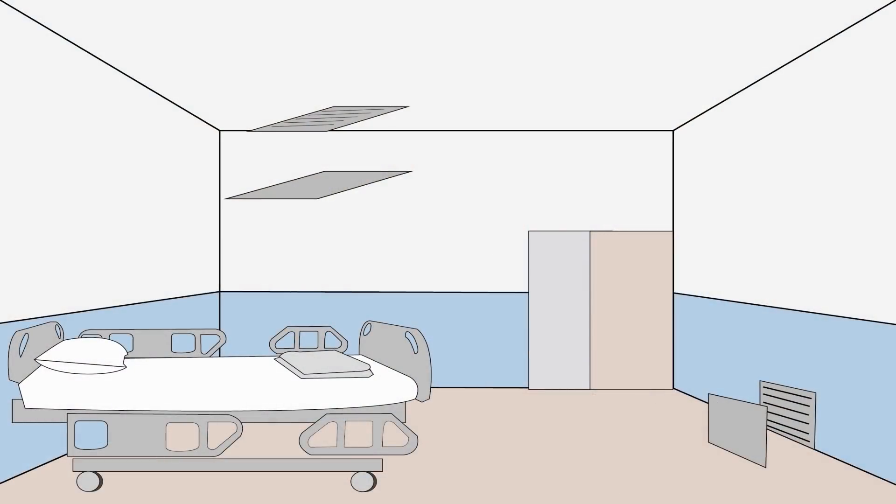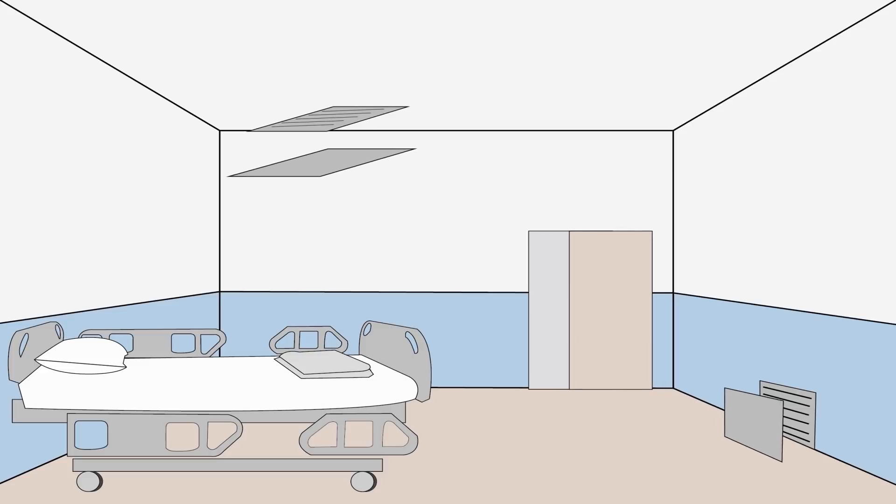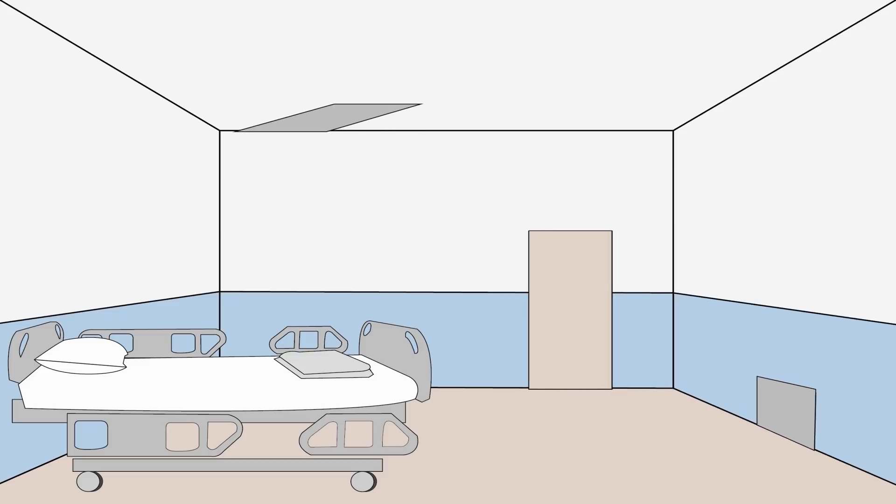To create an isolation space, you have to cut the room off from the rest of the hospital. You have to close off the HVAC system from the rest of the hospital so that you're not pumping central air-conditioned air from the hospital into it, nor returning air to the central system, because that's just going to be a means of cross-contamination and you're just going to move your virus all over the hospital. We shut it off, completely shut it off.